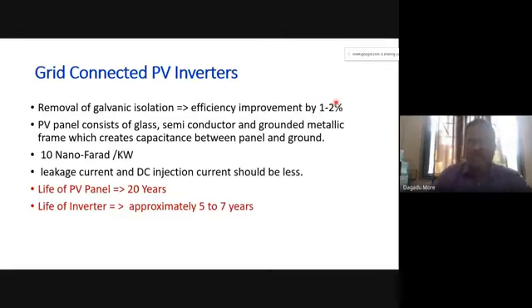Transformer efficiency is almost 95%. So the transformer efficiency may be 95-96%, but the overall efficiency of the system will be reduced by 1 to 2%. So we want to connect the inverter directly to the grid. We don't require galvanic isolation between the PV system and the grid.